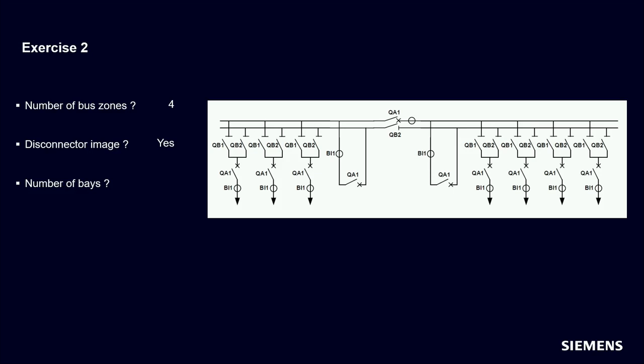Number of bays. Now I give a little time. So please count the number of bays. Okay, there are 11. I guess quite a lot of you may answer also that we need only 10 bays or only 8 bays. So let's count in detail. Here we have 3 bays. Here we have 4 bays. That's 7, 8, 9. And now it will be interesting. That will be 10. We need 1 dedicated bay for this real coupler with 1 circuit breaker and with 1 CT. But we need also 1 additional bay for the sectionalizing disconnector. If you have more sectionalizing disconnectors, you can use the same bay, but you need at least 1 dedicated bay only for the sectionalizers.